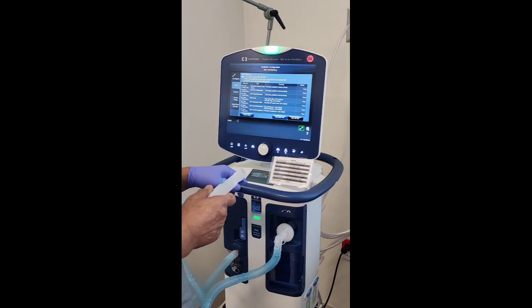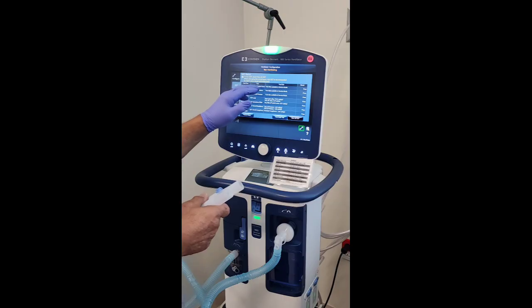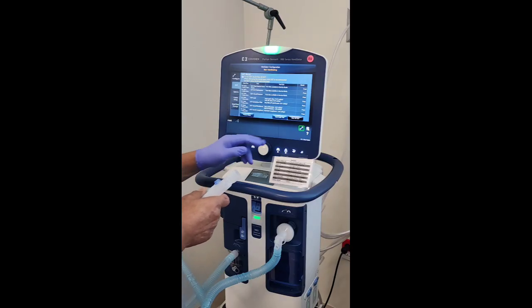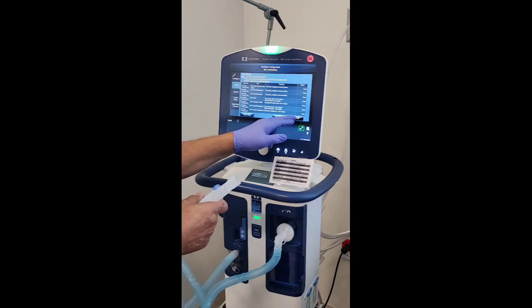It's going to go through a series of tests: the flow sensor, EV performance, circuit pressure, leak test, exhalation filter, circuit resistance, circuit compliance. And those are all the tests. Okay, so I'm going to go ahead and run it. Run all tests. And then you've got to accept. Basically, you're following every step it tells you to do.